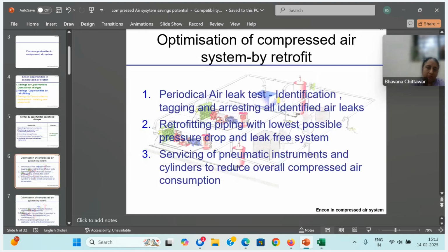Next one, optimization by retrofit. Retrofit again, periodical air leak test, identification, tagging, arresting all leaks. So why is it retrofit? I put leaks. Certain things, instruments, we can arrest immediately. Certain things, piping needs modification. You would have put union joints. It may be leaking. Some corroded pipe may be leaking, so the retrofit is required.